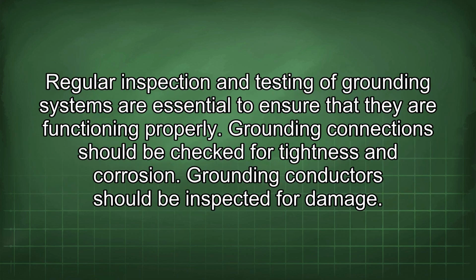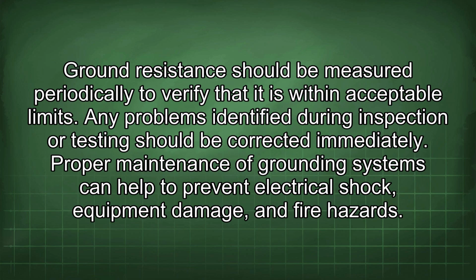Regular inspection and testing of grounding systems are essential to ensure that they are functioning properly. Grounding connections should be checked for tightness and corrosion. Grounding conductors should be inspected for damage. Ground resistance should be measured periodically to verify that it is within acceptable limits. Any problems identified during inspection or testing should be corrected immediately.